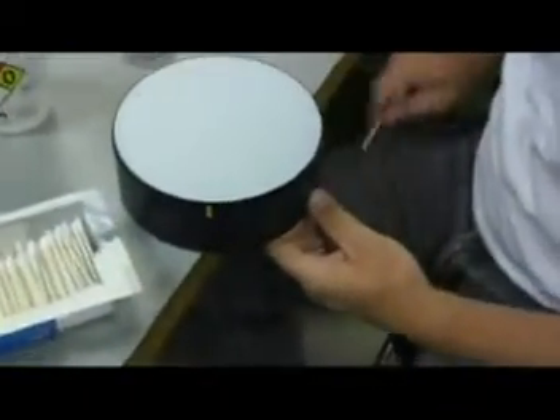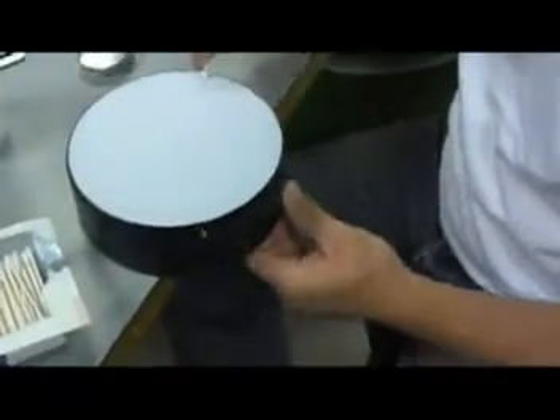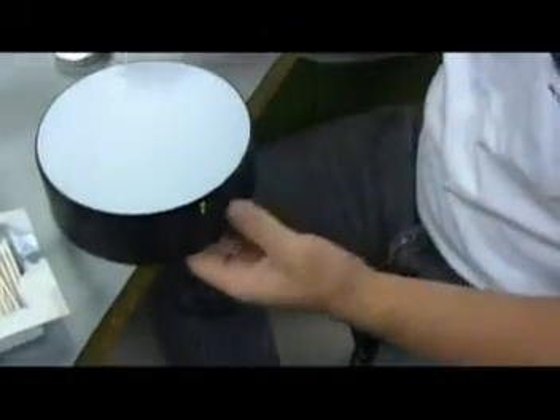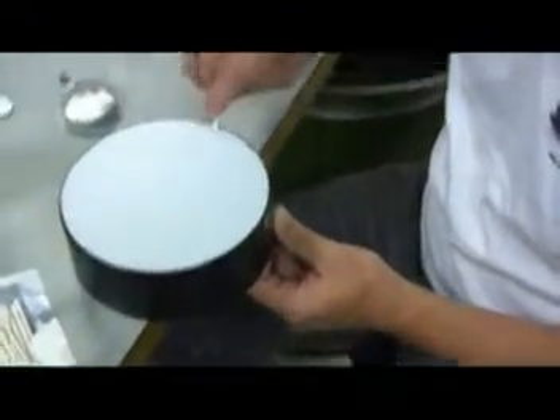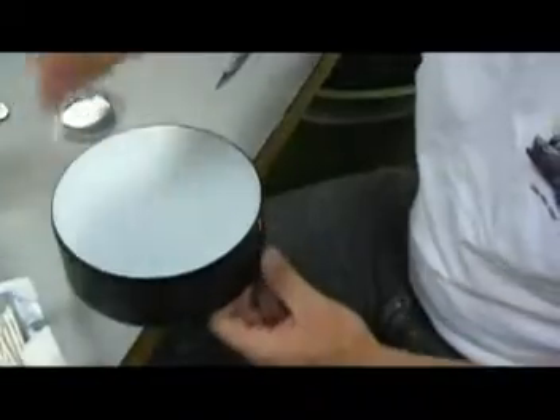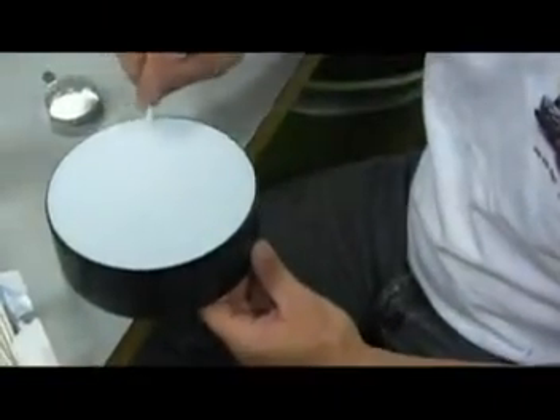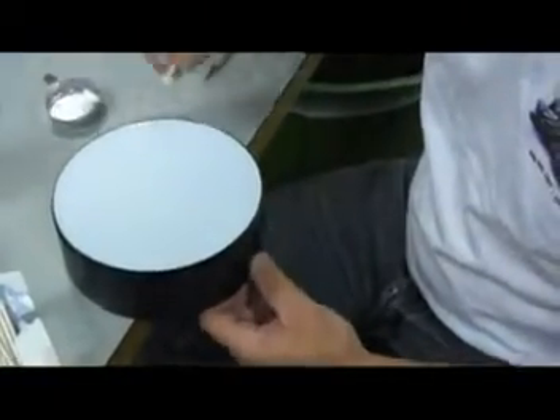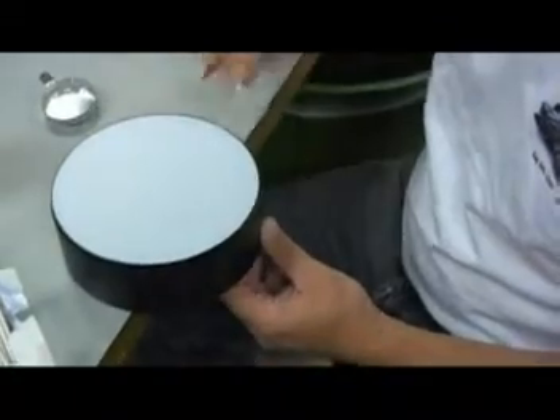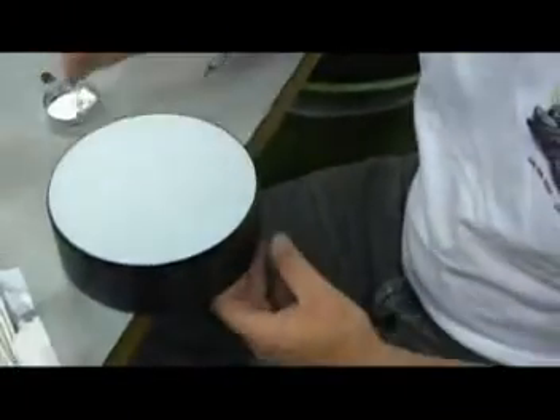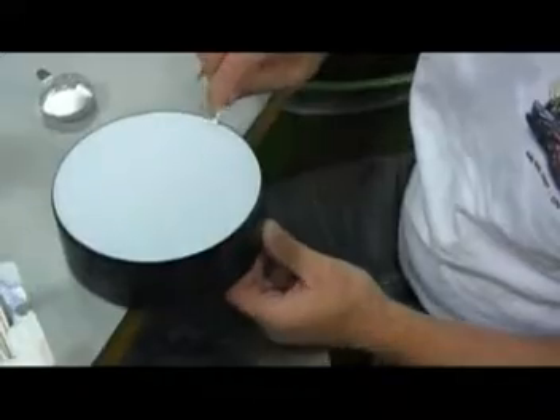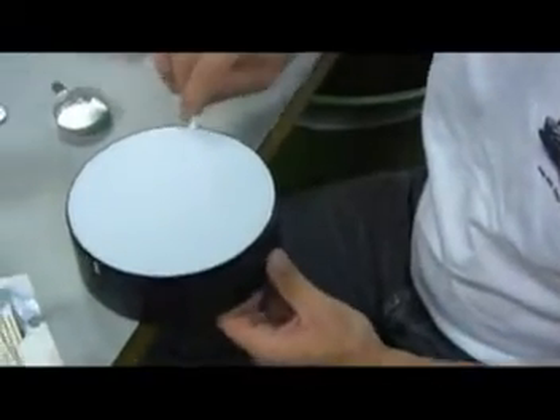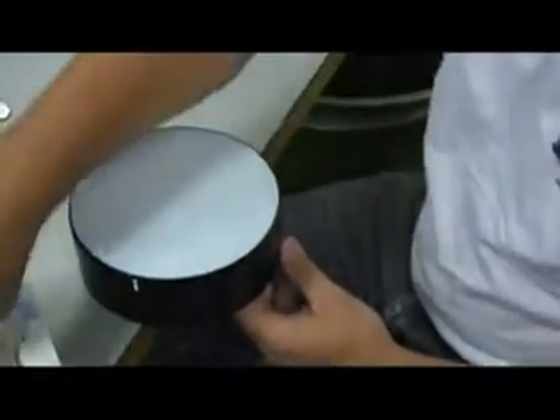Now we're going to take some isopropyl alcohol. When we press that cover into the holder, there will be some RTV that's squeezed out. We'll use our Q-tip now, a little isopropyl alcohol, and we'll clean off that excess. Nice and slow, take your time, and we'll have a cover that is as good as new.